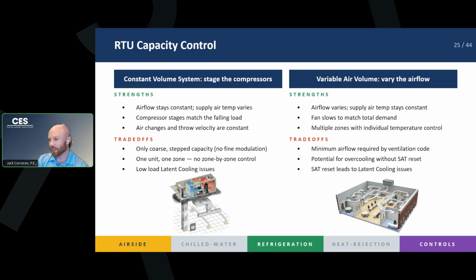And then on the right side, our variable air volume, our VAV system. I said this is a powerful tool. This is used a lot in our office spaces and in New York City. We're going to vary the airflow and keep the temperature of the air constant, right? So if a zone reaches the correct temperature, we don't want to send any more cooling. We lower the amount of airflow that's going to the zone, and less cold air will allow the space to maintain or get a little bit warmer.